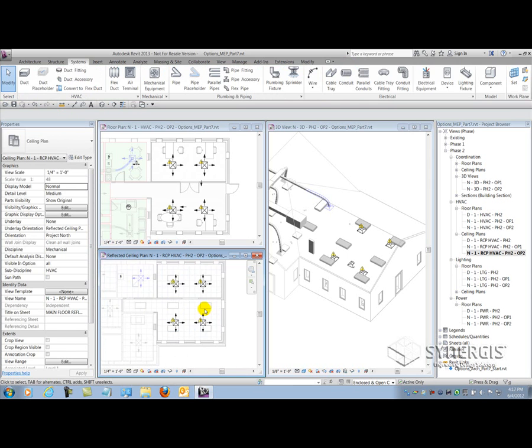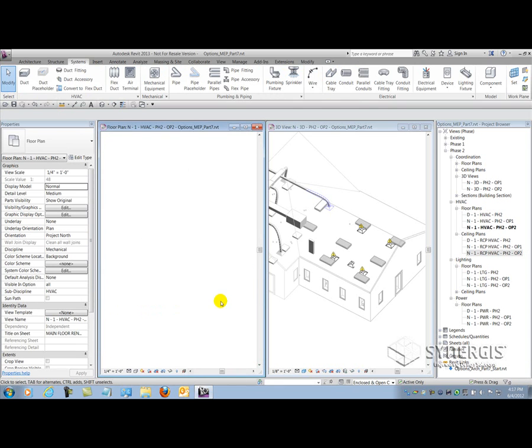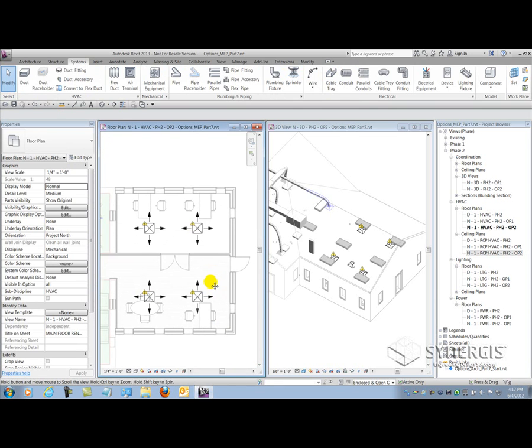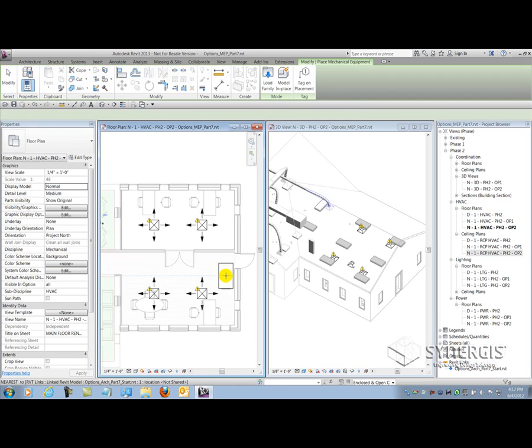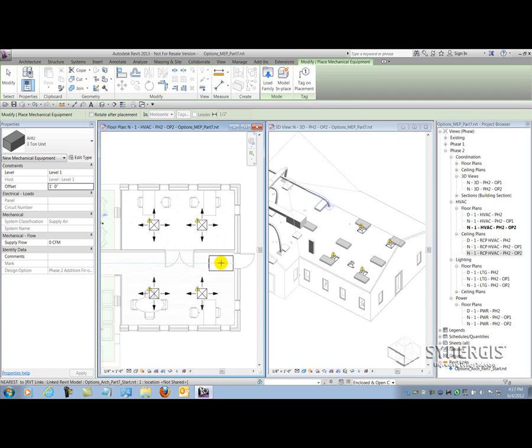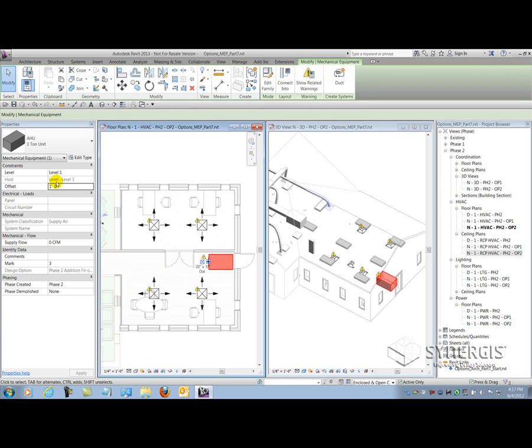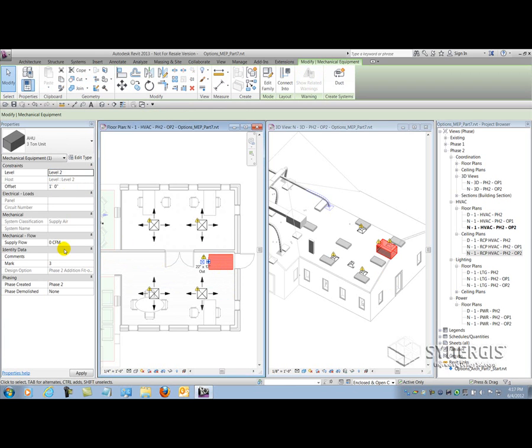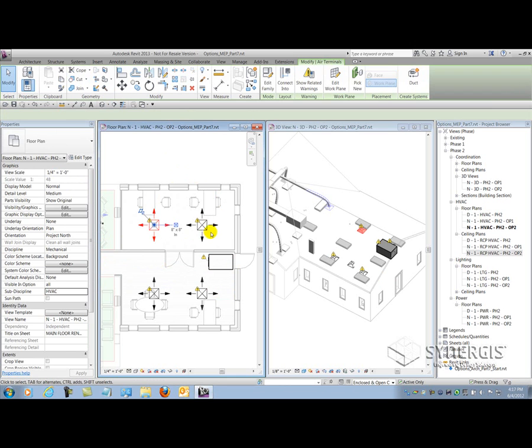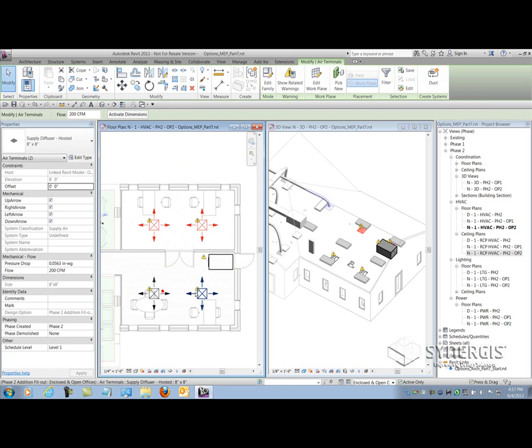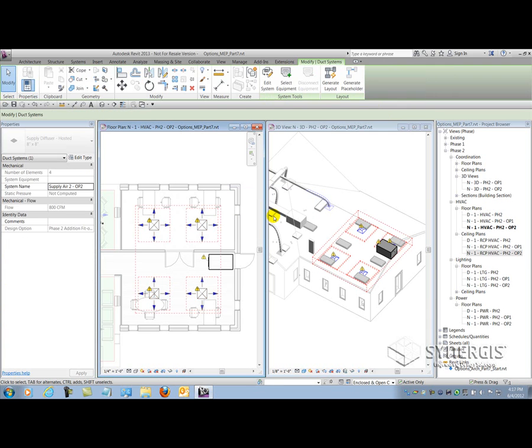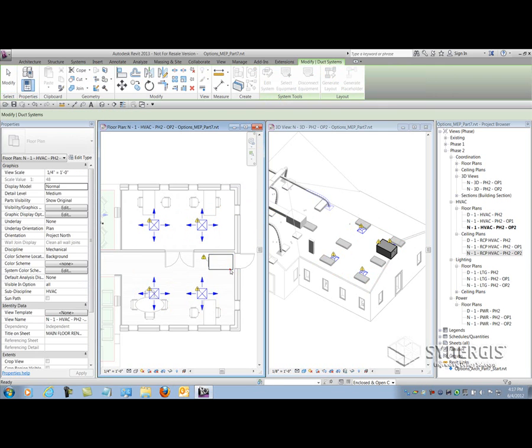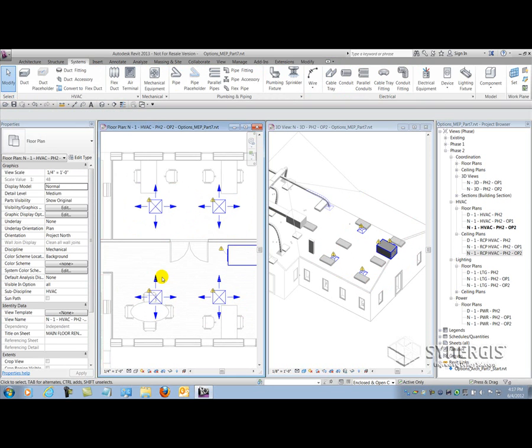Now that I got my diffusers in, I can lay out my equipment location for this layout. I'll go to my mechanical equipment, rotate around, make sure it's on the right level and offset. Then change the number back to two because that's also only the second air handling unit, even though it's in a different option. Then I'll go make another system. I'll pick those four devices, create a duct system. This will be option two. I'll select the appropriate equipment for that system, and now I can draw my placeholder duct.